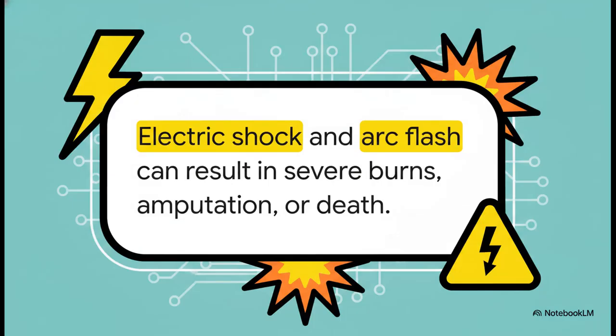The guidelines laid out pretty bluntly: working on or near energized electrical equipment without proper isolation carries absolutely severe risks. We're talking electric shock, devastating arc flashes, severe burns, loss of mobility, amputation, and yes, death. A lot of totally preventable incidents happen when equipment was supposed to be de-energized, but was somehow inadvertently switched back on. This isn't just theory, guys. These are the very real physical consequences that demand immediate respect before you even unzip your tool bag.